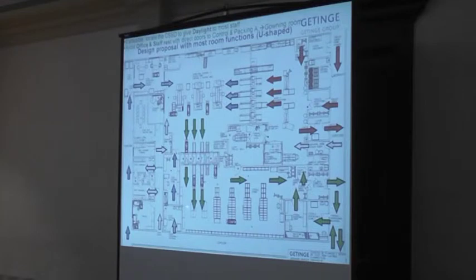So here we will actually not be able to walk between. We have a window. One person working here takes up the outer box, removes that, and then we bring in the clean material through the hatch to the conveyor belt so we can slide it over like that. In that way we separate this a bit dirtier area from the clean material store here, where we have storage, and we bring in what we need to the packing tables. Here we have some small amount of items just for daily use, and then we bring more the next day. We can have a trolley standing with those items, like wrapping papers with the tray, for example, and other items.